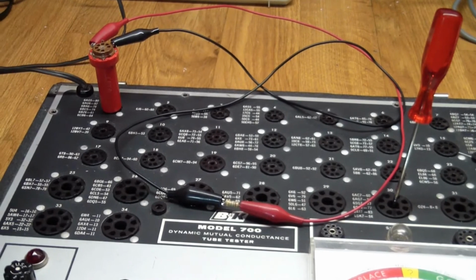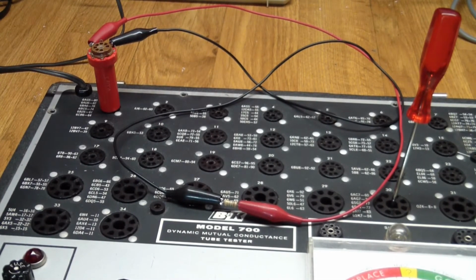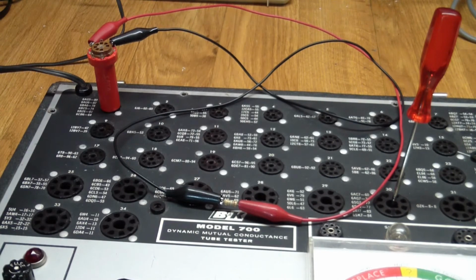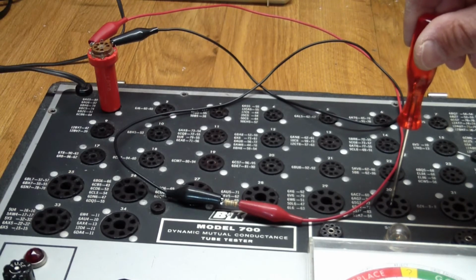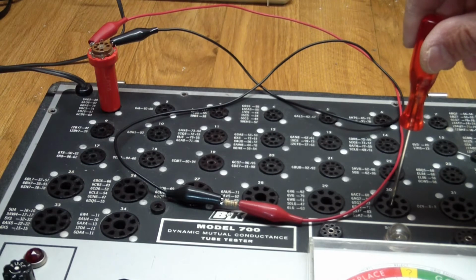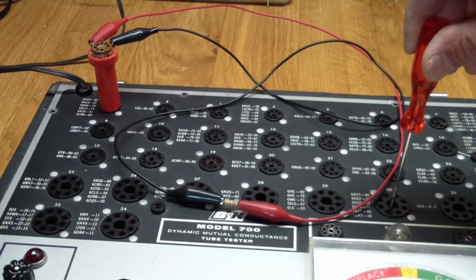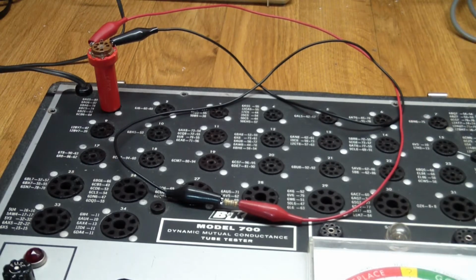The first calibration step is called the short sensitivity adjustment. What we do here is set up the short indicator bulb. We adjust that, and the way you do it is you connect a 1 megohm resistor between pins 2 and 4, and then you press the shorts button and observe the shorts lamp. So when I press it, you can see it comes on. Can we adjust it? Yes, till it just turns off, and then we're supposed to bring it back so it just turns on. Don't know if you can see it, but it's off, on. There you go. That completes the first calibration step.